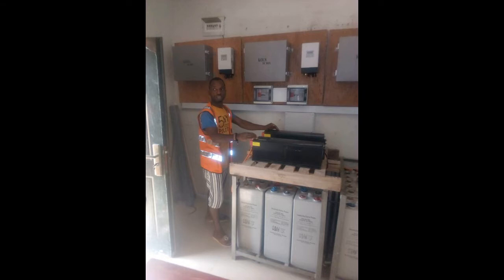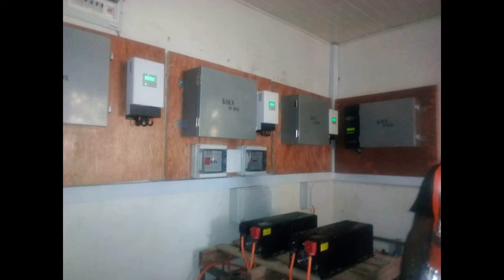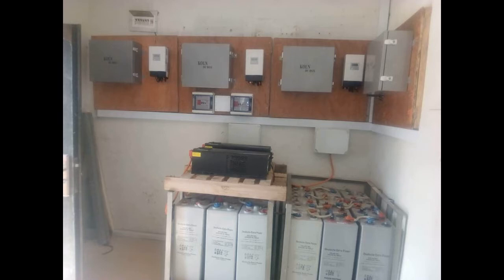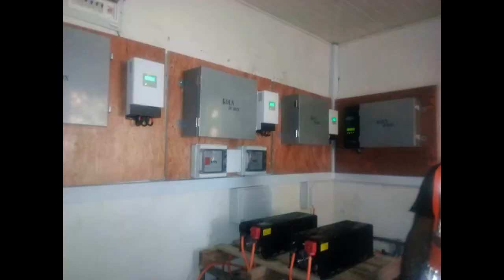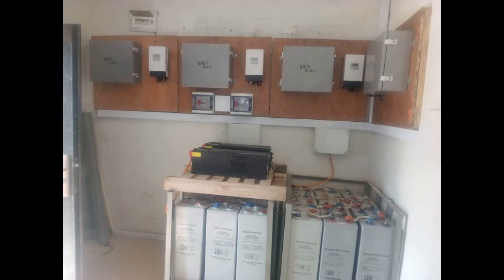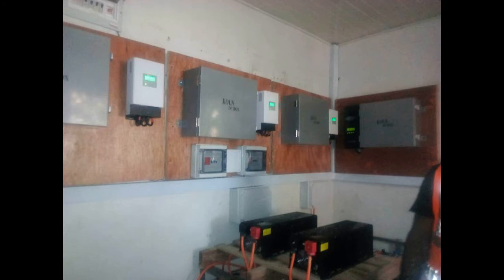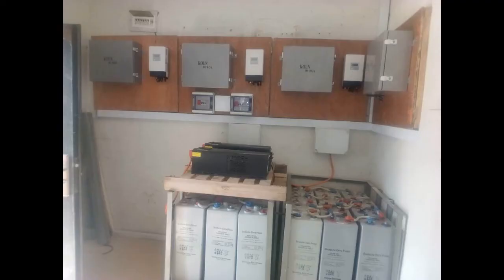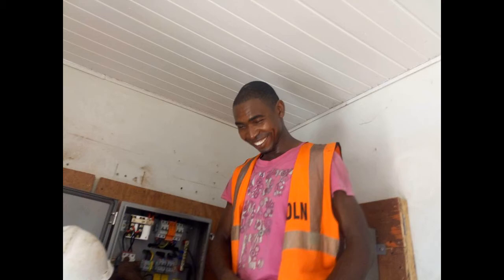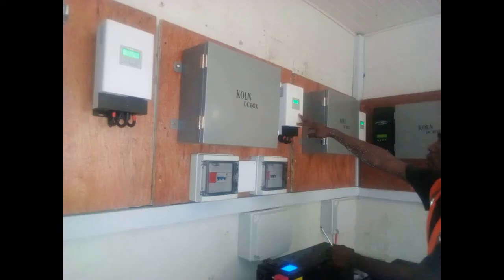Unfortunately, you can't see the photograph of the battery breakers further down that picture, but you can see the battery bus bars, the 2 boxes ahead, both positive and negative. Just a very comprehensive installation, using genuine components, good design, within tolerances and maximums of equipment, so that things just work like clockwork. So the 2 7.5 kVA inverters, 1000 amp hour 48 volt battery bank, and supplying this house of all the circuits, air conditioning, you name it. We're quite pleased with this installation, to be honest, and so was the homeowner.